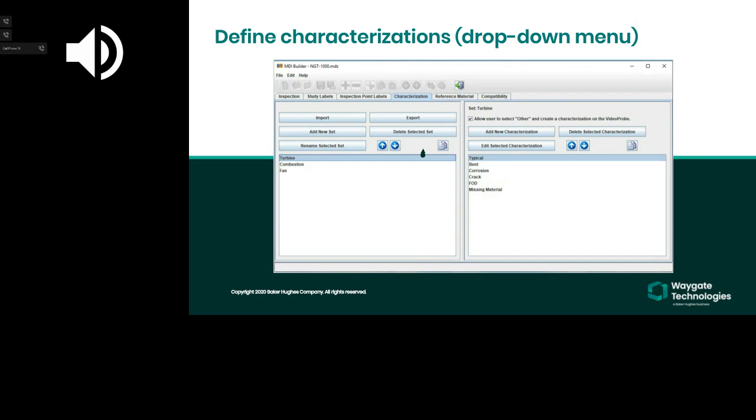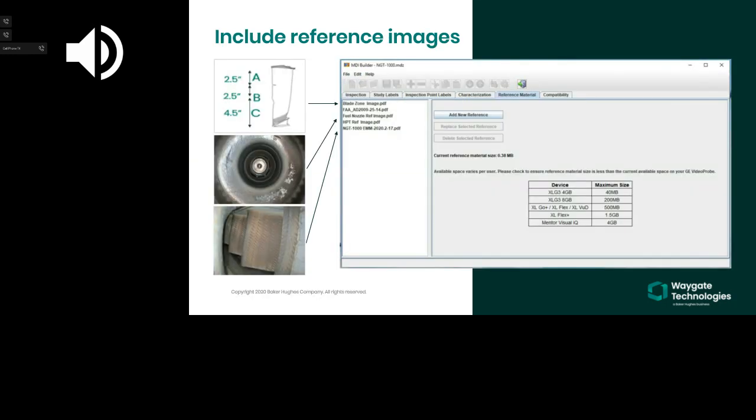Then in those same manuals, it says inspect this area, and I want it to look like this, and you can put reference pictures, whether they're JPEGs or bitmaps. You can put reference material, and it's always best if it's marked for reference only, because if it becomes outdated, that can present its own set of issues to be mindful of.